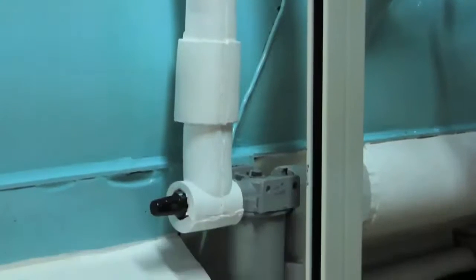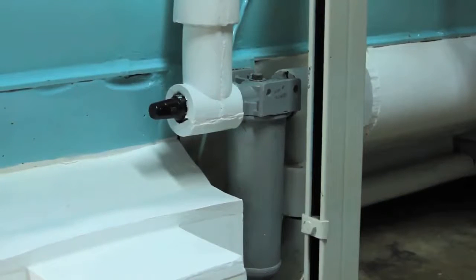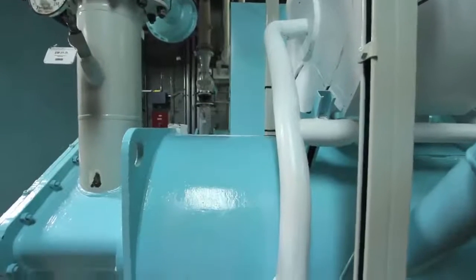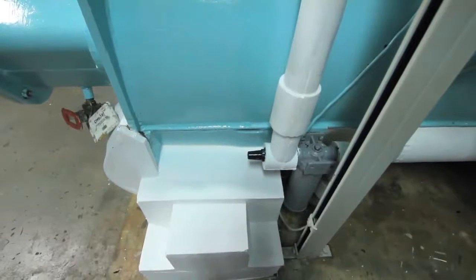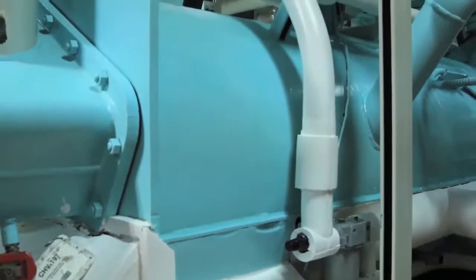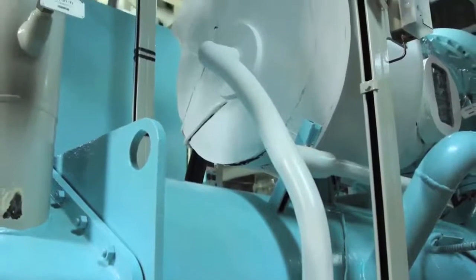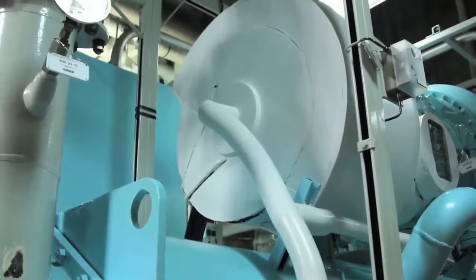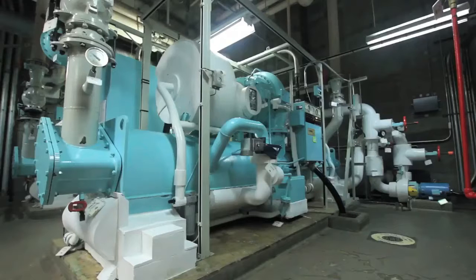The refrigerant filters ensure gas cleanliness. They remove contaminants and foreign material from the refrigerant. Contaminants within the refrigerant system will reduce the longevity of this machine. Any foreign material will cause problems, whether from physical debris or chemical introduction into the system, which will form acids and will corrode the inside of the machine. The windings in this motor are very susceptible to dirty refrigerant. Only clean, dry refrigerant and the appropriate refrigerant oil should be in this machine.